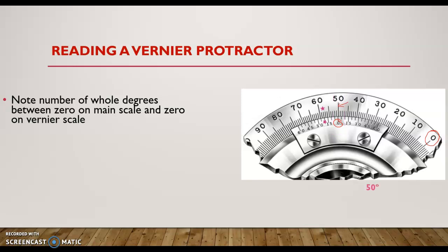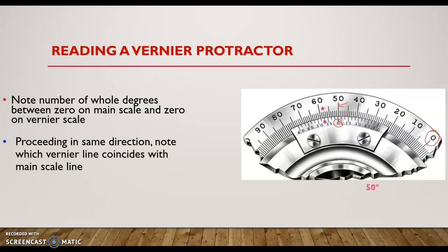Next, find the vernier scale reading. Proceed in the same direction as the main scale reading — here, counterclockwise. When moving counterclockwise, consider the left-side vernier scale. When moving clockwise, consider the right-side vernier scale. Note which vernier line coincides with a main scale line.